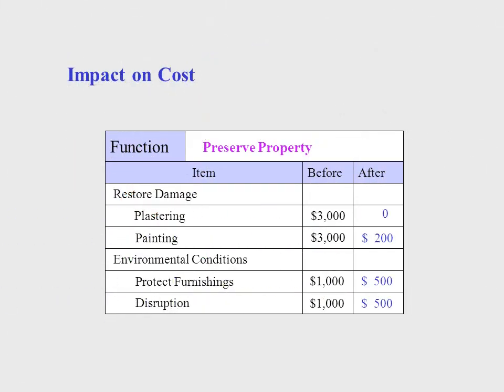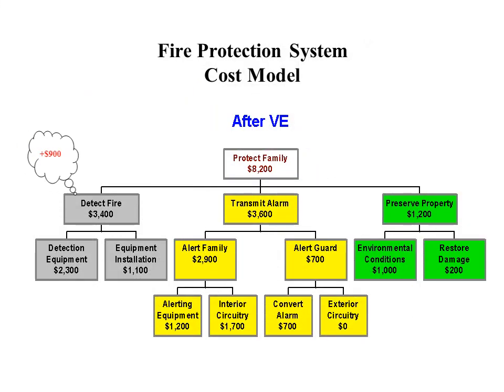The original $8,000 cost to preserve property was reduced to $1,200 without the sacrifice of function. But even more important, we had eliminated all craft trades but the electrician, who by union rules could drill holes and spray paint the mounting bases. We rebid the project to electrical contractors rather than general contractors as prime. The bids this time came in $1,800 below budget. The cost of our basic function, Detect Fire, increased by $900 and represented 41% of the cost — much better value.